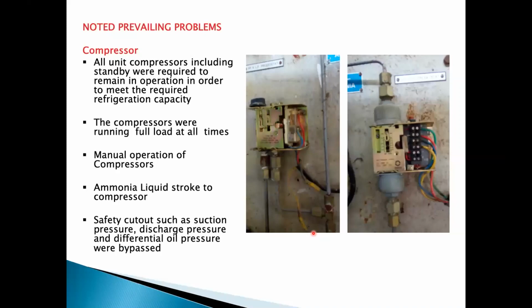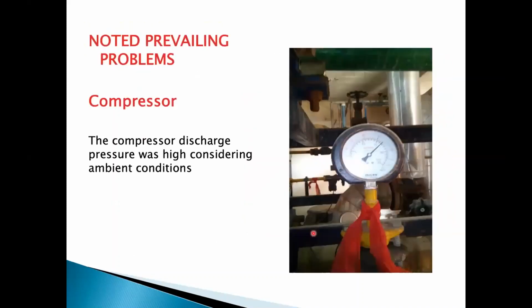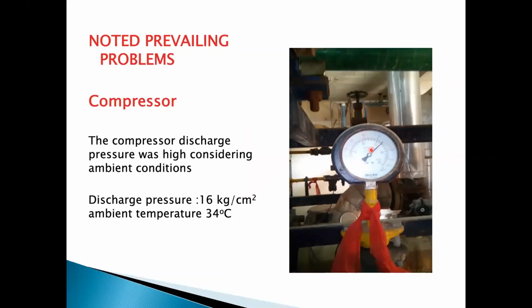The safety systems, particularly the safety cutouts provided to the compressors, were bypassed. The main reason for the bypass was that the compressor was operating at a very high discharge pressure and very low suction pressure, almost 16 kg discharge pressure and minus 0.1 bar suction pressure. This is the actual photograph of a pressure gauge showing 16 bar operating pressure. The ambient temperature, being in Odisha near the seashore, was 34-35 degrees centigrade, so theoretically it should be around 30.